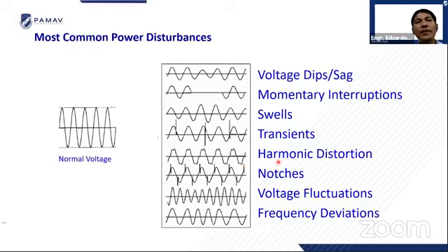Here we have the harmonic distortion. Nowadays, most of our motors, because we need to install VFDs for precision, like in a manufacturing plant or industrial plant, you have a VFD. So with VFDs, we know that they give harmonics. And we know also that the 5th and 7th are the harmonic content of most VFDs. So if we have a VFD in our system, we expect that there's harmonics in the system. So we have to mitigate that kind of harmonics.